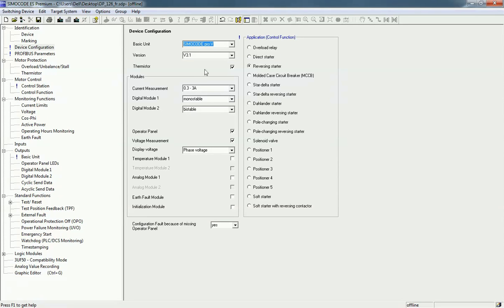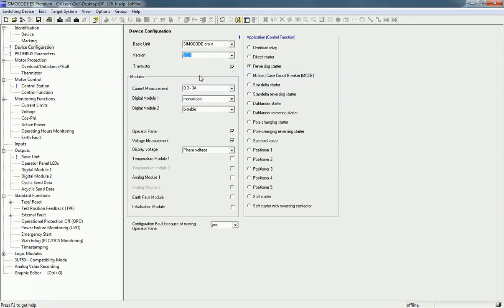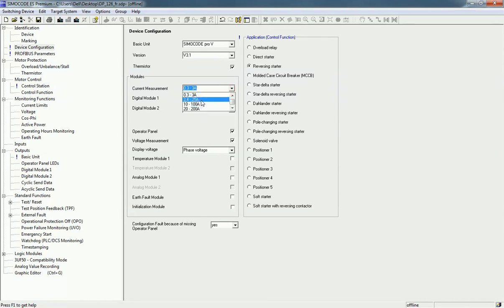For the version, we will select 3.1 as per our hardware. For the current measurement unit, our SIMOCODE kit has a 0.3 to 3 ampere capacity, and based on the current module you can select the appropriate module type range.